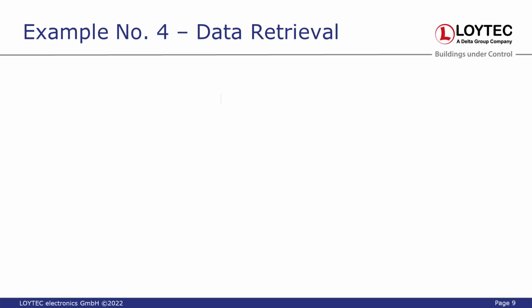Either the property, like in this case present value, is being subscribed via COV, which means change of value. So as soon as the server object or client mapping changes its value, the counterpart is being COV notified and also sent the value.